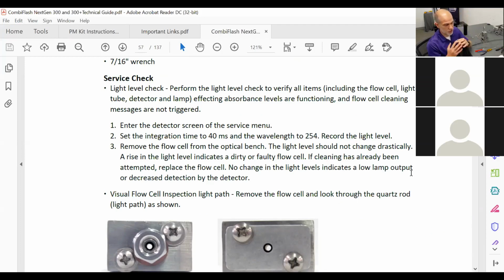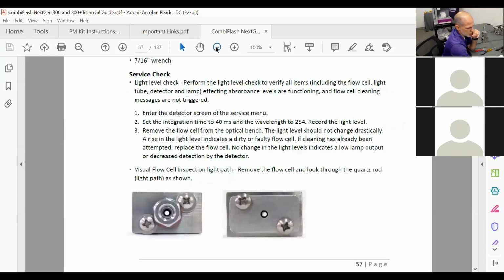So what this is telling you, and this is something that I talk people through on the phone all the time, is you want to shine the light through the flow cell. Tell me what you're reading at 254, okay? Let's just say, to throw a number out there, it's 1200. Now, if you take that flow cell out and you shine light directly on the detector, all of a sudden it's 35,000, or 3,500, sorry, then you know that your flow cell is prohibiting light from getting through. So it needs cleaned, it needs replaced maybe. Some kind of service needs to happen, because your flow cell should not be stopping all of that light from passing through, okay?